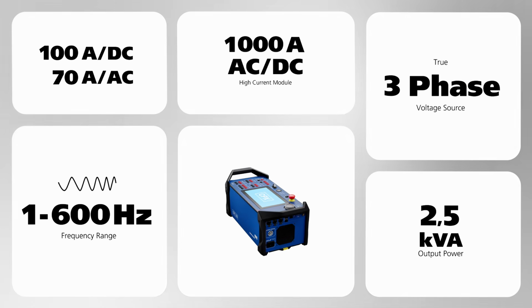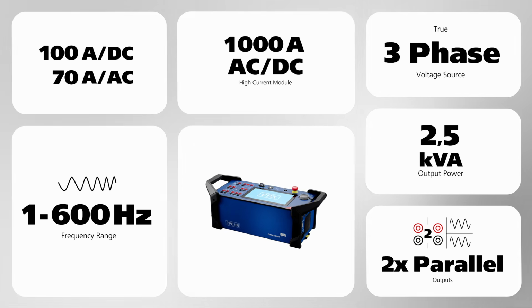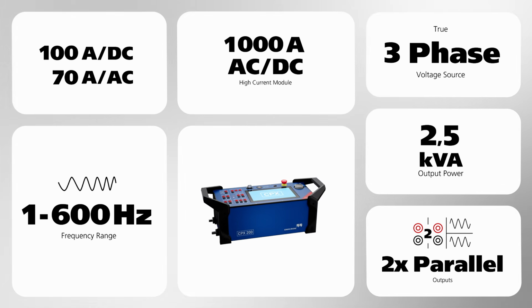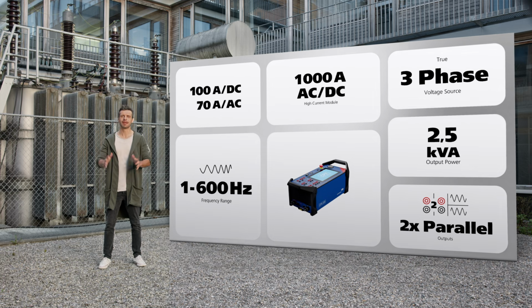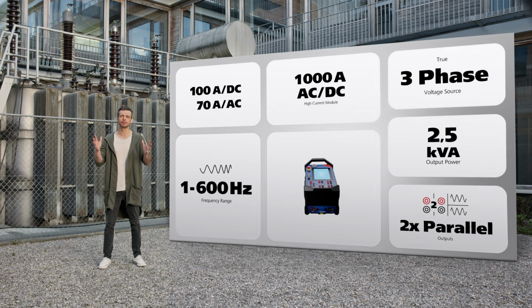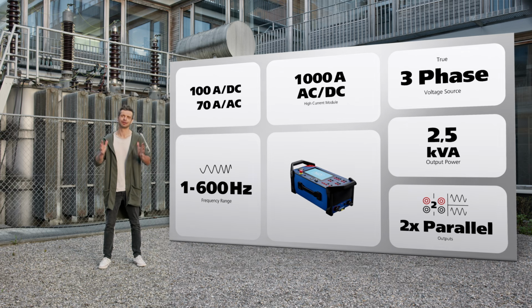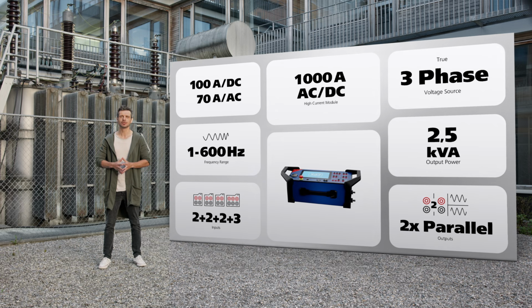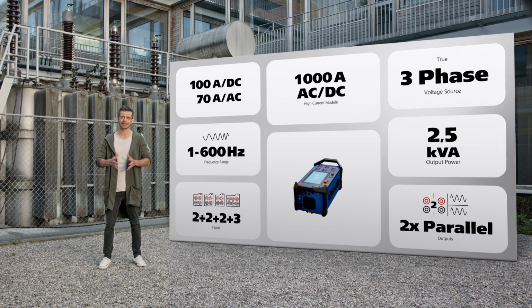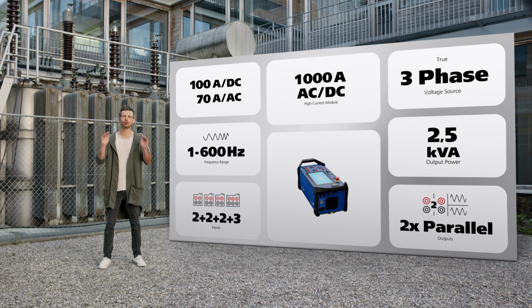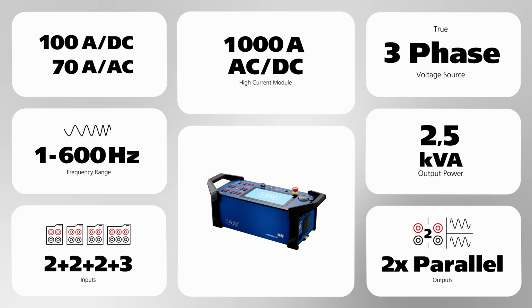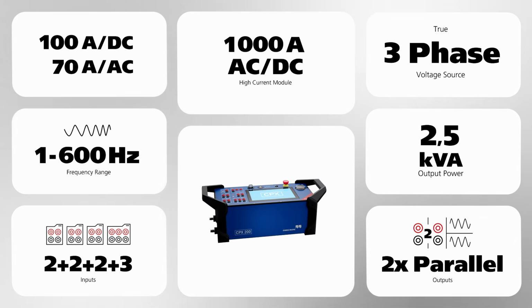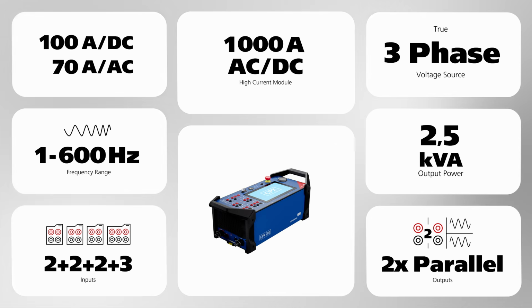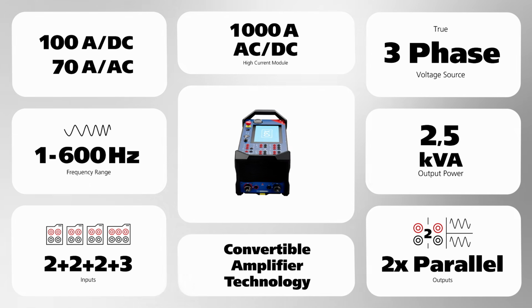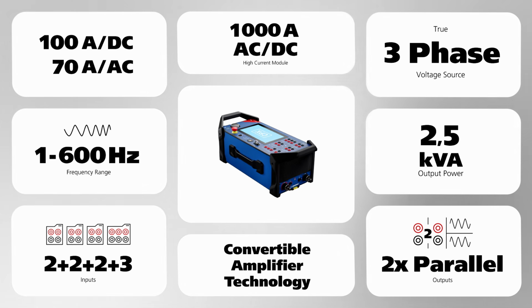The CPX can also run two output sources in parallel, providing a significant advantage for directional overcurrent protection relay tests. Complementing the powerful testing functionalities of the CPX 200 are two highly accurate current inputs, two highly accurate voltage inputs, two binary outputs with integrated current measurement, and three multi-purpose binary inputs, making the CPX a true all-rounder in all kinds of applications. To build a device so small yet so flexible, we developed a totally new convertible amplifier that is not only immensely powerful, but also breathtakingly accurate.